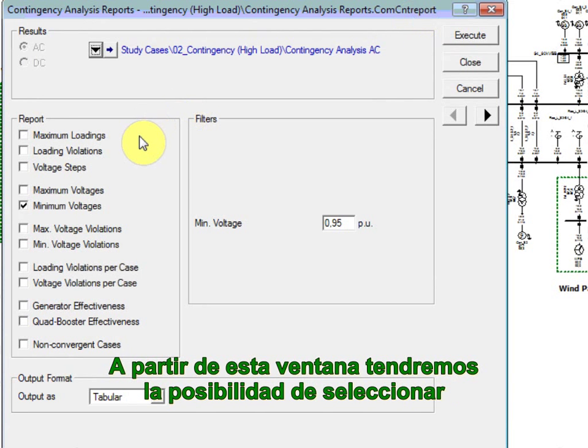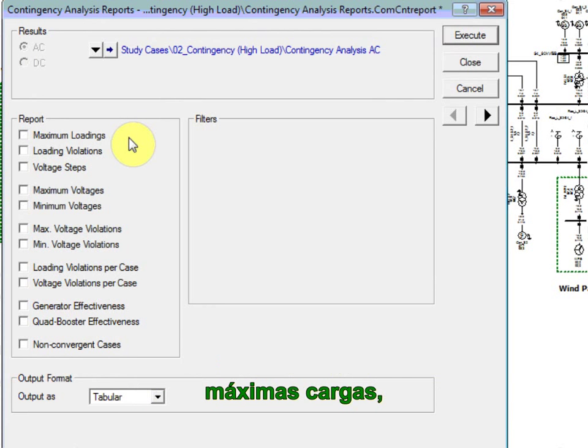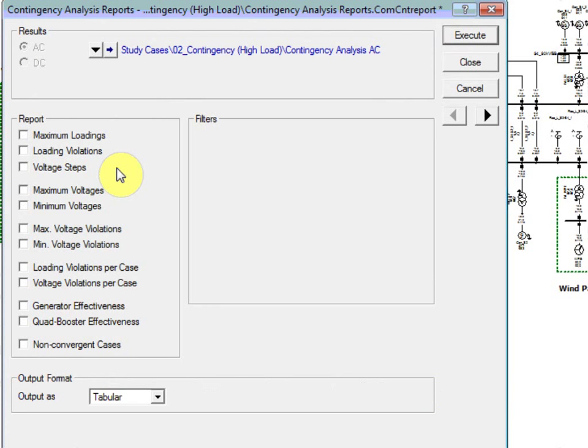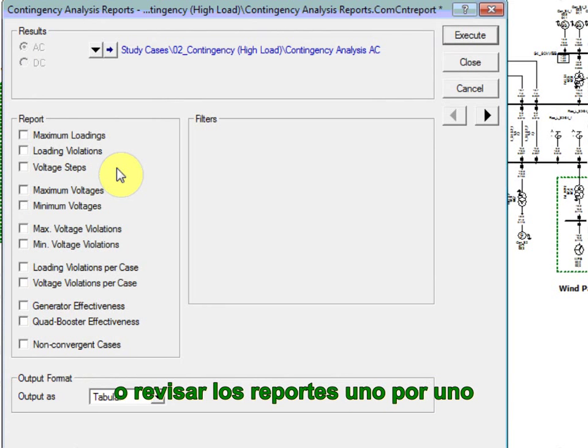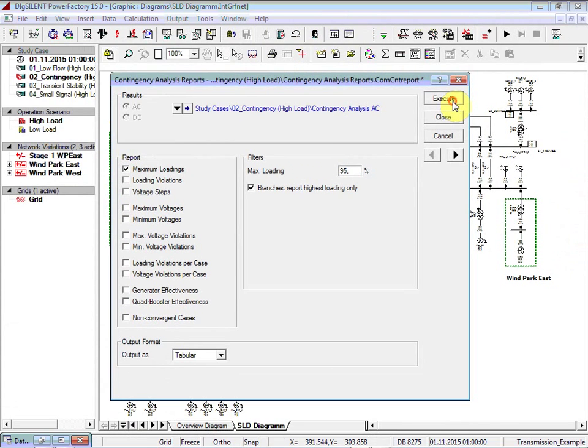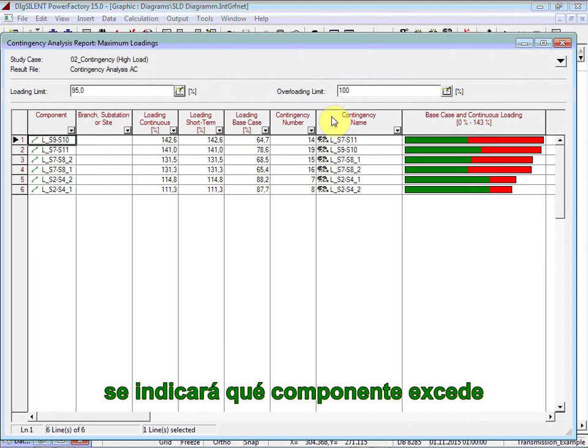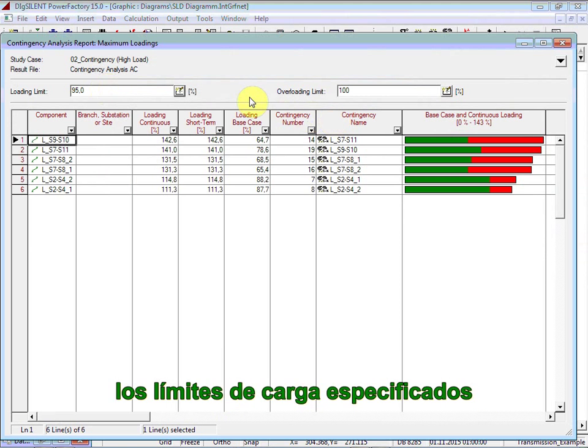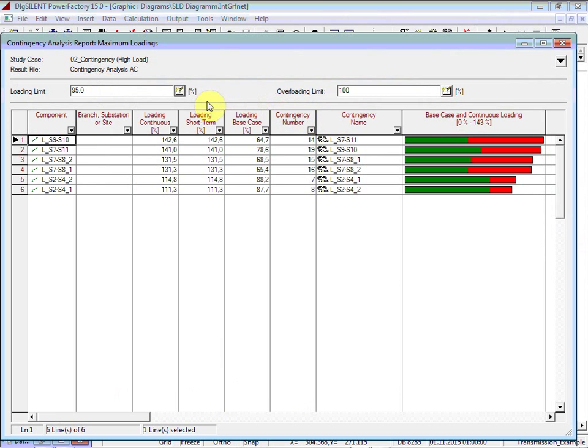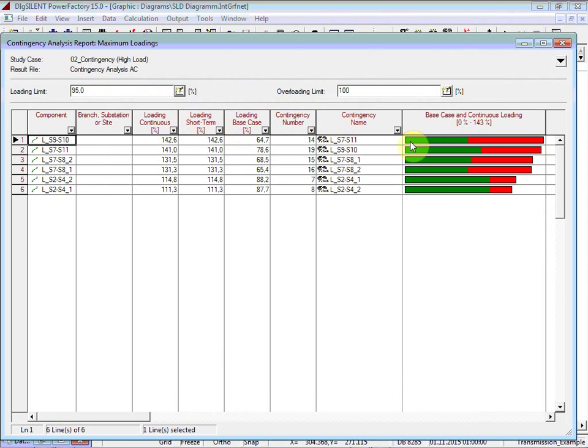The results of the contingency analysis can be displayed by clicking on the report contingency analysis results button. From this dialog, we have the possibility of selecting between a list of predefined reports, such as maximum loadings, loading violations, maximum or minimum voltage, etc. We can either select a group of them or look at the reports one by one. In the case of a maximum loading report, we will get indicated which component exceeds the loading limit specified. Additional information such as continuous loading, short-term loading, the loading on the base case, and the contingency name will also be displayed.